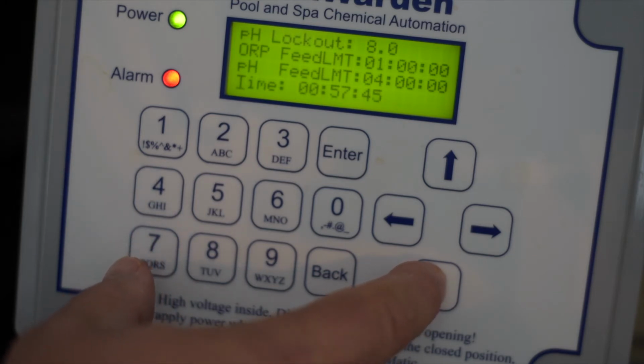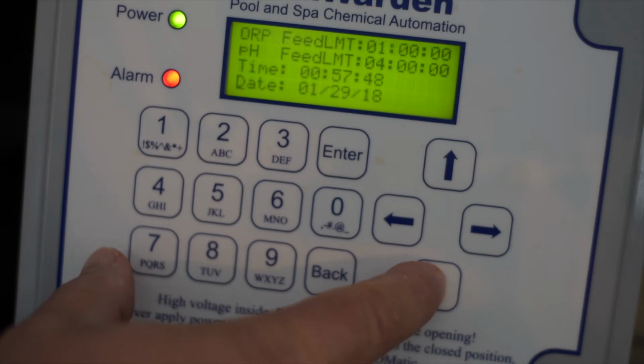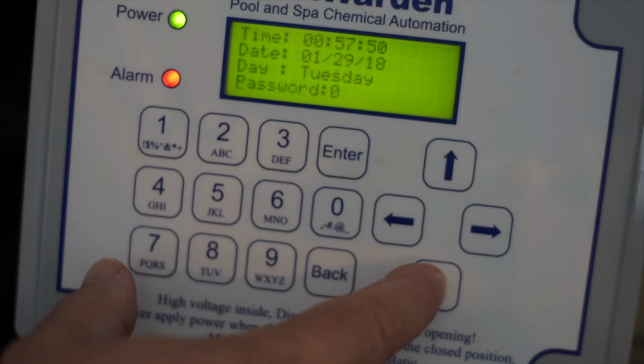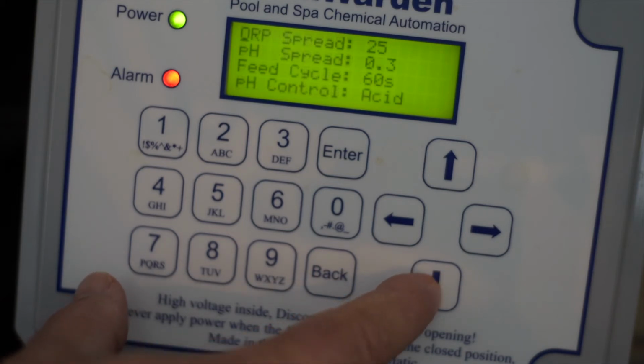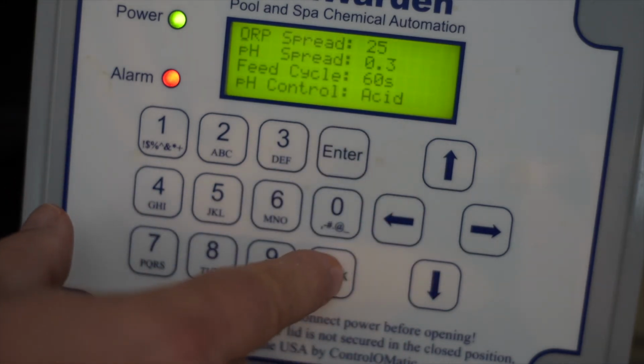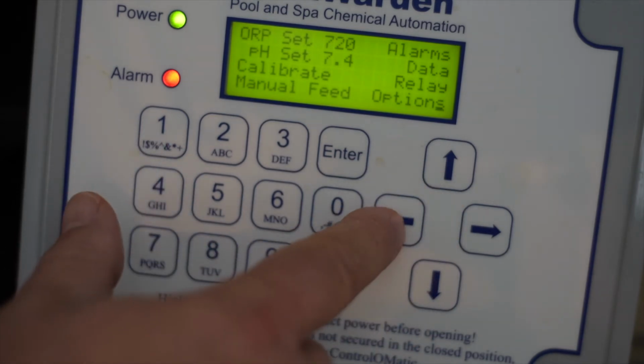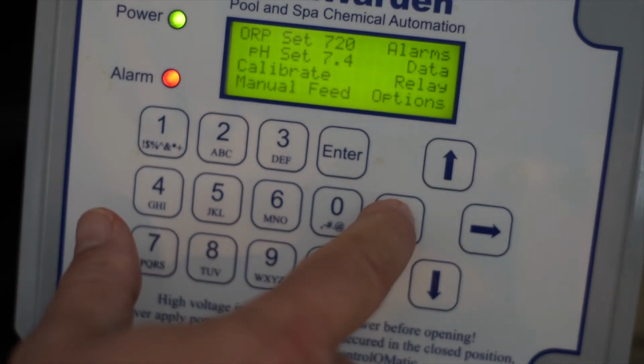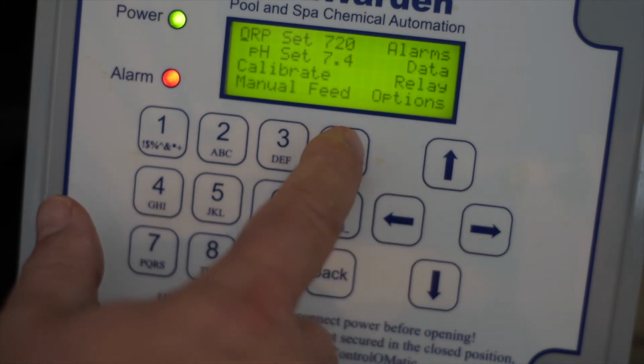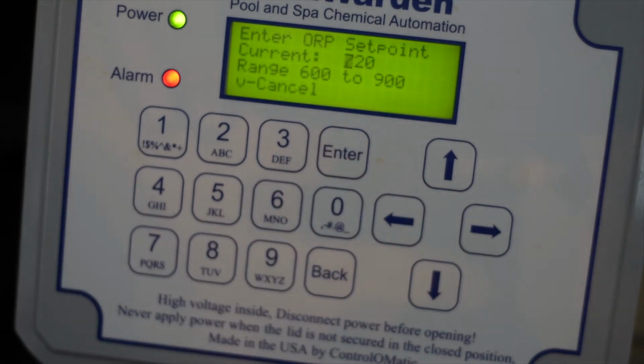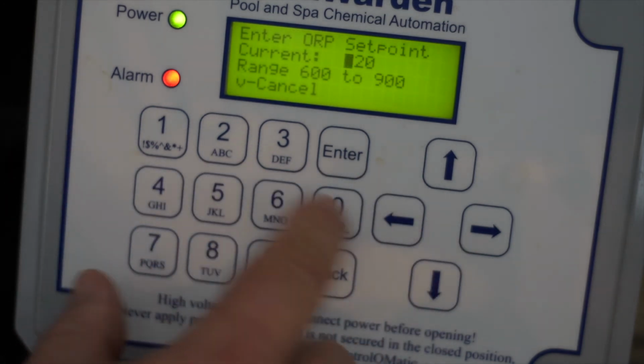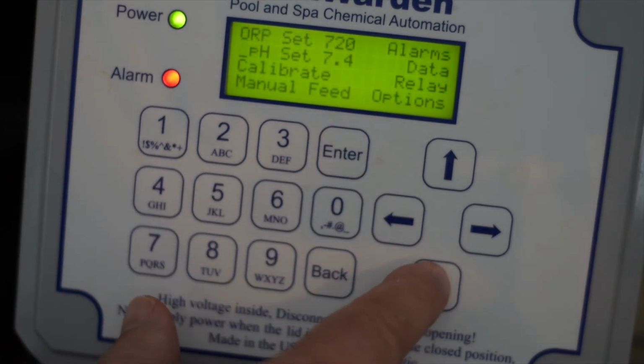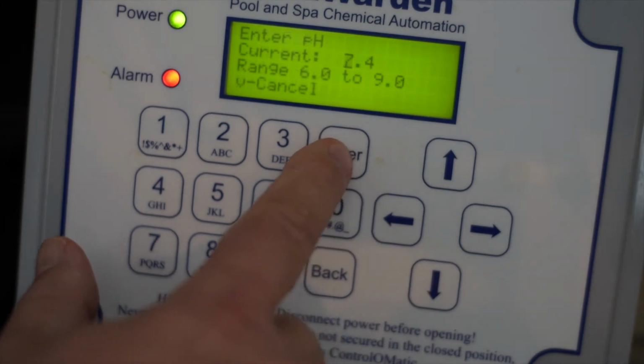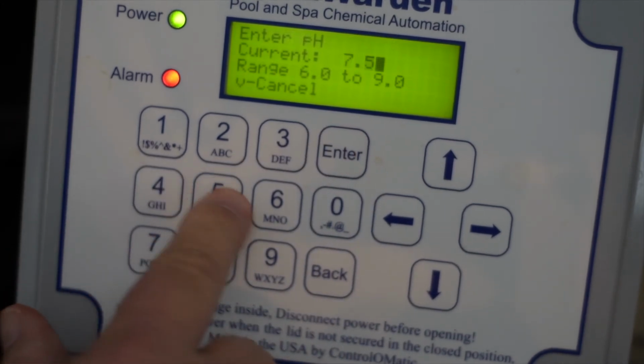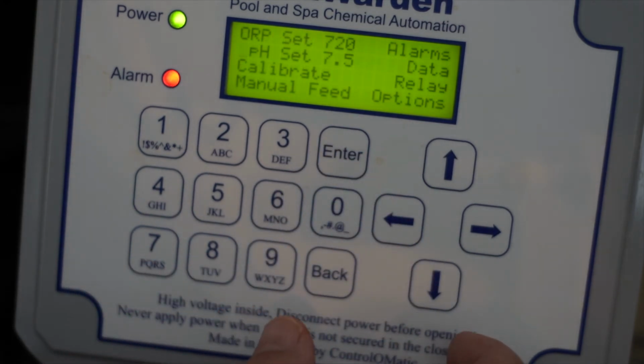Okay, there's also entering the time of day, the date and day of the week, and then there's also a password. So doing that, and then going up to your ORP set point, change that number to whatever you want. Same thing on pH. Let's say we want that 7.5.